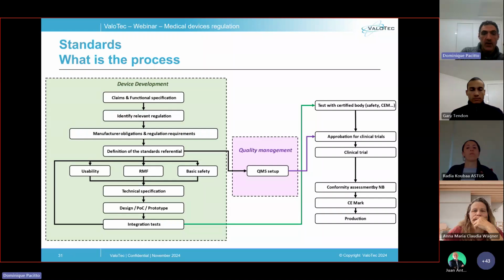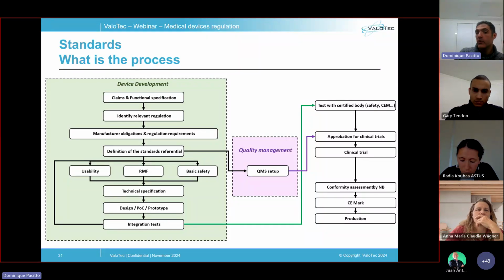The second step is to apply the regulation requirements. This consists in applying all we saw during this webinar: for example, identify the device class, fulfill the manufacturer obligation, identify the requirements according to Annex 1 of the regulation, and identify the associated standards that fulfill this requirement.